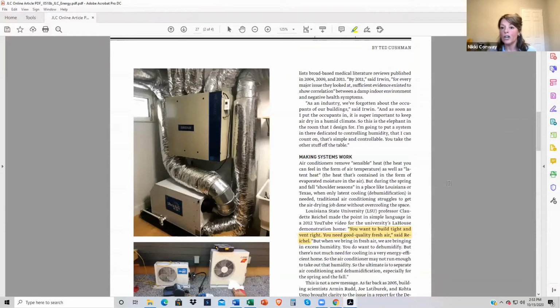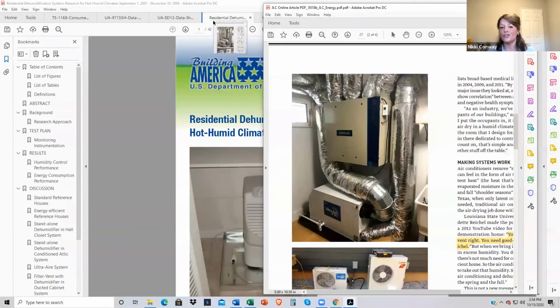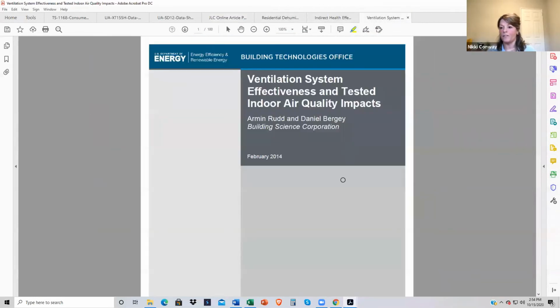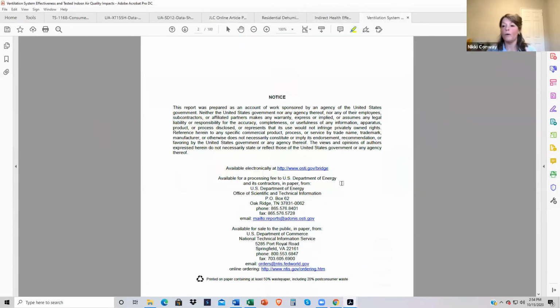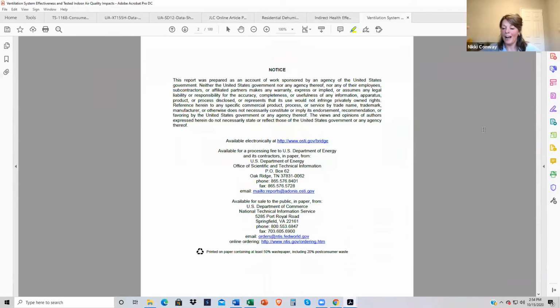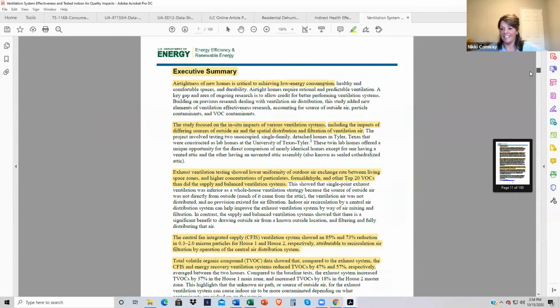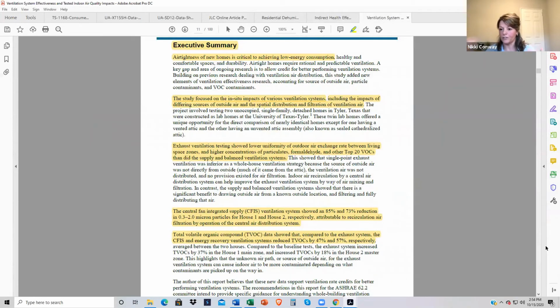Now, most homes aren't tight enough that... in a warm, humid climate, the recommendation for ventilation is to achieve a slight positive pressure on the house. We want to stop the hot, wet air coming in through our walls as much as possible. We have so much negative pressure going on in our homes—we've got bath fans, kitchen hoods, dryers—so a lot of the time our houses are sucking in air through the cracks and crevices, and that air isn't being filtered or conditioned.